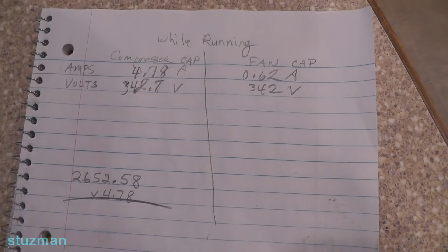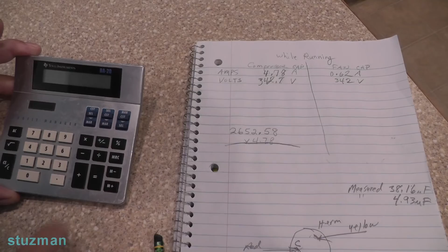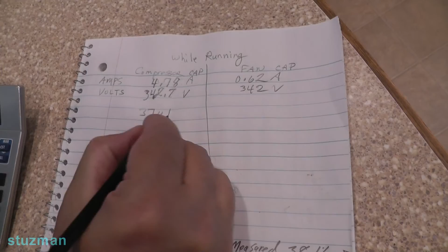Now we are going to divide the number that we get over here by our voltage of 342.7. We divide it, and we get 36.998. So we just rounded off, say 37 microfarads, okay? So this one over here, 37 microfarads. Now you see we measured with a capacitance meter 38.16 microfarads. So we're 1 microfarad off, well within tolerance.